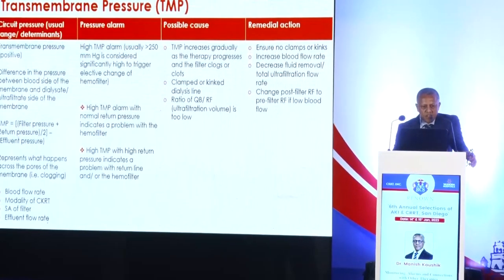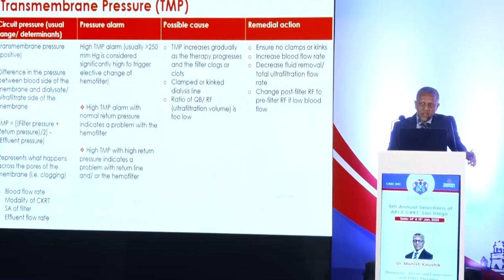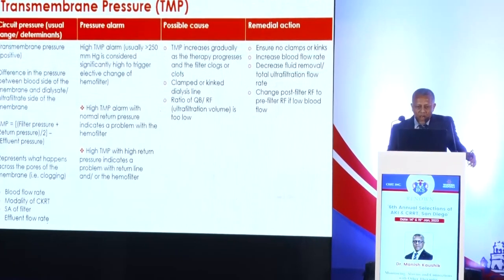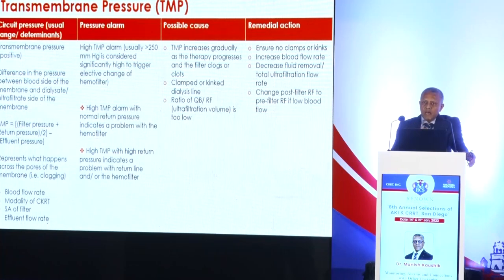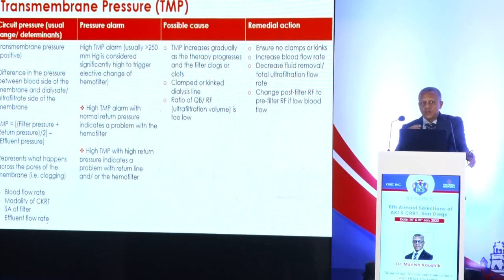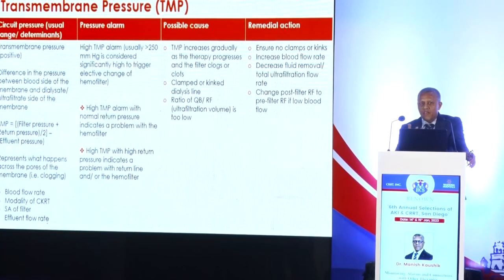Transmembrane pressure is the difference in pressure between the blood side and the dialysate or ultrafiltrate side of the membrane, representing what is happening across the pores of the filter. Major determinants include blood flow rate, modality of dialysis, filter surface area, and effluent flow rate. A progressively increasing transmembrane pressure beyond 200–250 mmHg suggests that pores are essentially all clogged. To generate the desired convective flow becomes very difficult, and some fibers may be clotting, reducing the effective surface area available to deliver the prescribed dose.